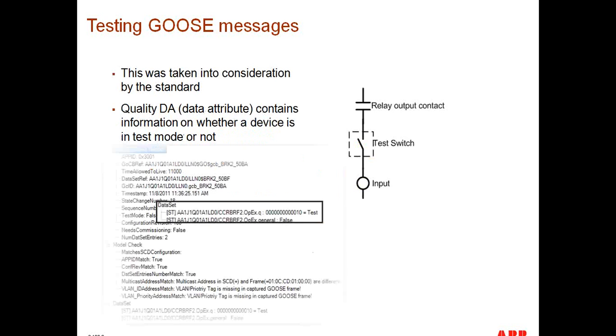Well, one of the key aspects when the standard was being defined was the need to have a mechanism to indicate that a device is in test mode. And the way this information is shared is via the quality. So when we look at the quality of a device, that's part of the data set that's being transmitted, we could see whether the device is in test mode or not. And in turn, the device that's being tested should change its quality from good to test in such a way that every device that's using this GOOSE message should be able to identify that this device is being tested, and in turn should not react to that information if that is the desired behavior.